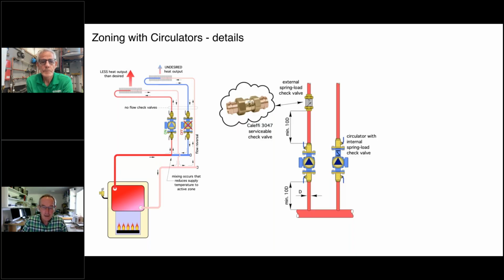A couple things on that. In general, when we're placing circulators in a system, we'd like to see a minimum of 10 diameters of straight pipe on the inlet of the circulator. It's simply to calm down turbulence that would occur, for example, here at a T in a header or through some component. And also we'd like to see some distance between the outlet of the circulator and the inlet of a check valve, so we don't get turbulent flow going directly into that check valve.